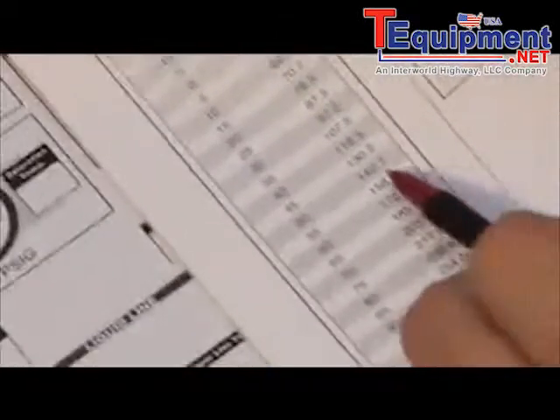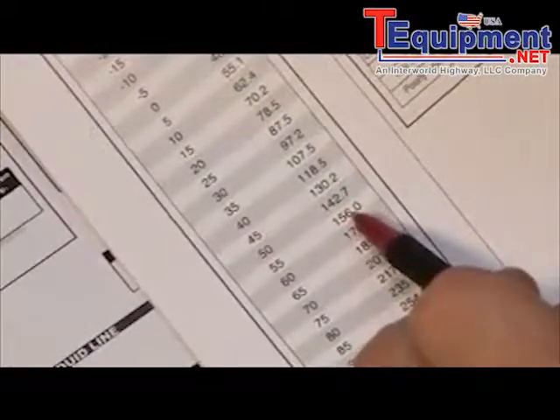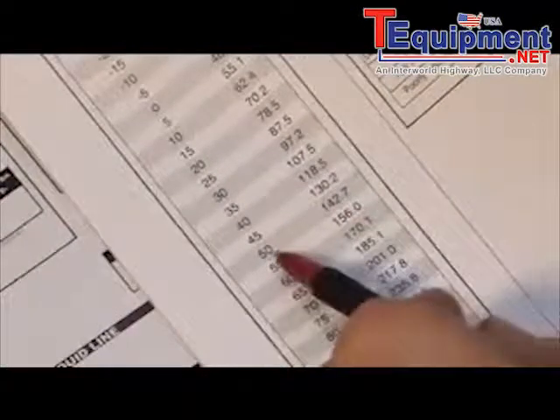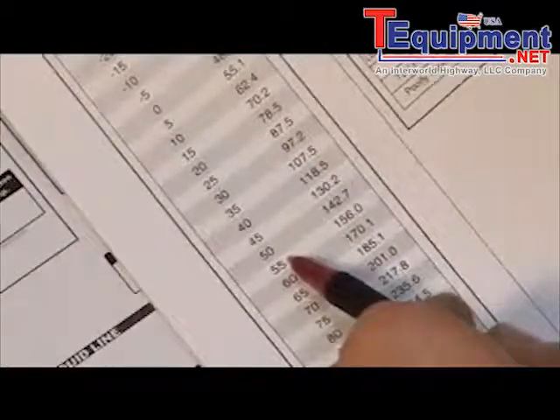The next thing is to find our saturation temperatures. We'll have to interpolate what the reading really is because 150 is not on the chart, so we're somewhere between 40 and 45 degrees. I'm going to estimate about 44 in this case, and we'll go ahead and record that on the sheet.